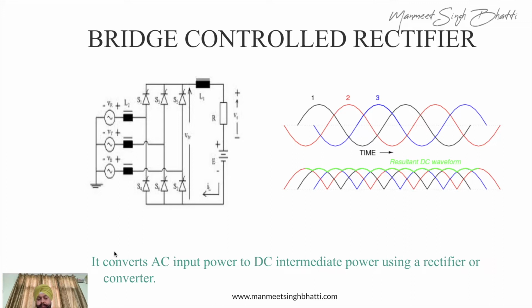So what happens is, if you see, we have a three-phase motor, so we have three-phase power coming in. So you have the RYB phases. All three phases which are giving power go to the bridge control rectifier. We are controlling the complete AC, and from the AC we convert it to DC. AC is sinusoidal in nature, and the DC waveform is on one side of the voltage, so it will be either positive or negative.